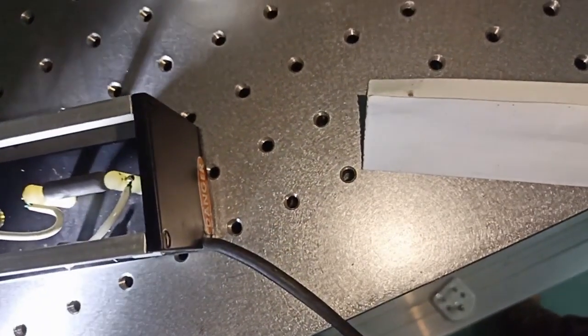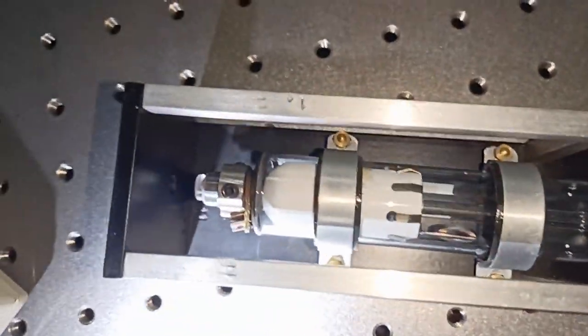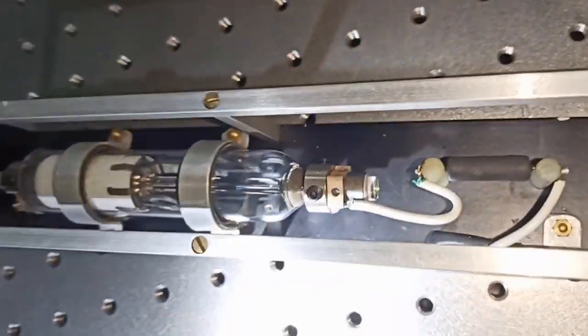Speckles are random diffuse patterns of light which may occur due to dust deposition in partially reflecting mirror and optics. So we need to clean it. Let's open it.